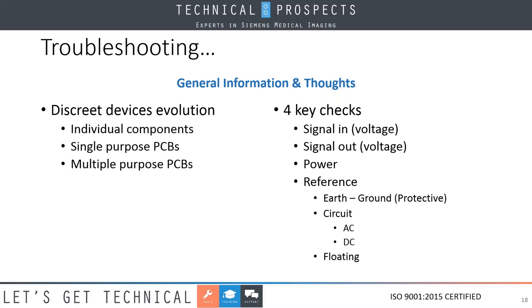The fourth one is reference. Notice I've broken this down to earth, circuit, and floating. These are not the same. Earth ground is protective. I know in our Siemens world, they call that PE ground. This is used for equal potential so that none of us get zapped when we're touching the machine. Because we have AC and DC circuits in there, you've got two different forms of reference.